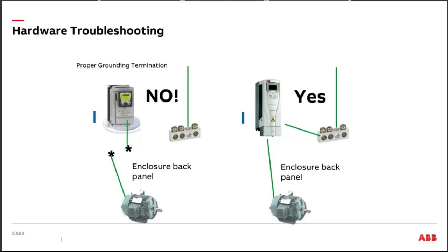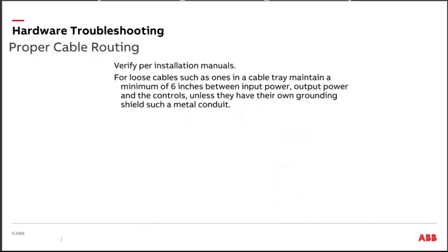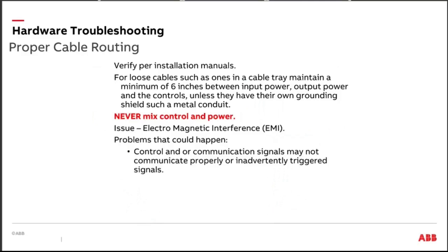We need our motor leads and we need a ground lead. Okay, and that ground wire needs to go back unbroken. Okay, when we're talking about cable routing, we want to make sure that we're following the manufacturer's recommendation. The hardware manual is your best friend, okay?